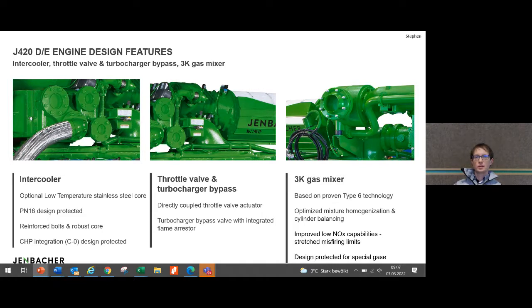Then moving a little bit backwards in the air system, we have the gas mixer, which is a completely new concept from the Type 6. The so-called 3K gas mixer improves quite significantly the mixing performance and therefore also the balance between the cylinders. That has allowed increased power at low NOx, which Stefan will talk about in a little bit more detail. At the same time, we've also design protected for special gas, especially coal mine and wood gas. These are now an integrated part of the concept.